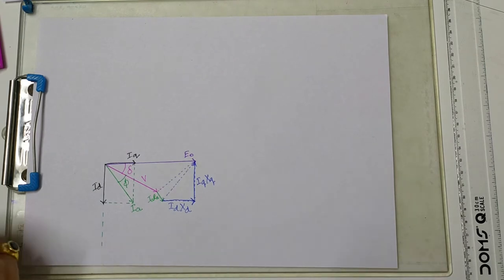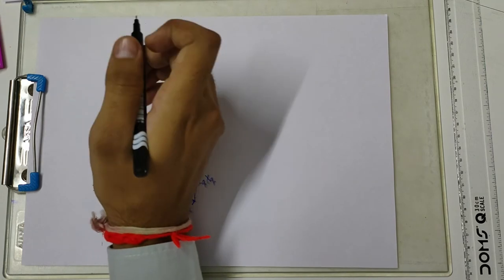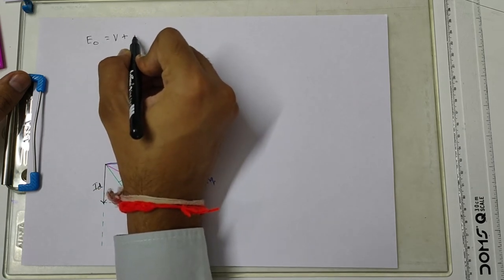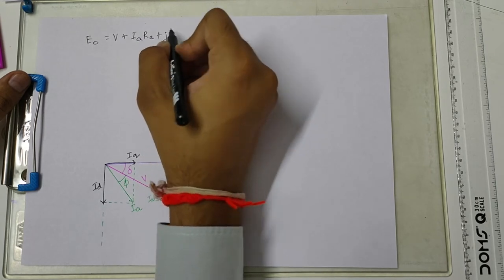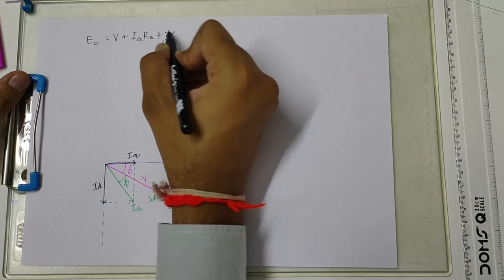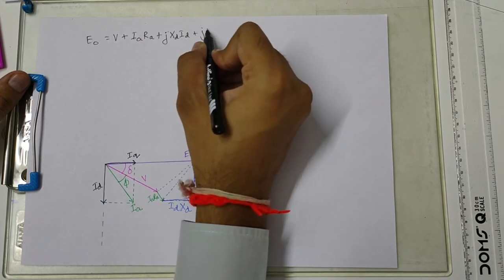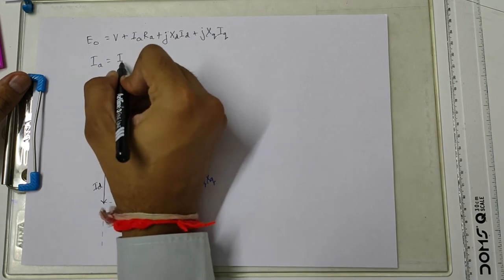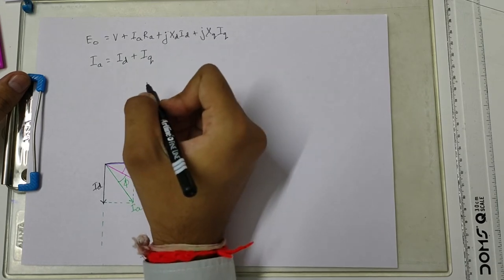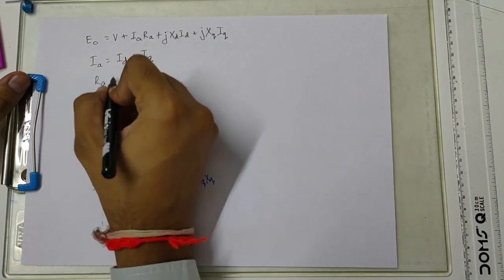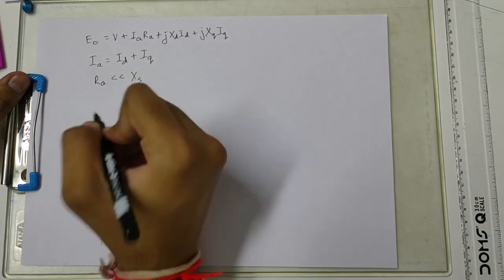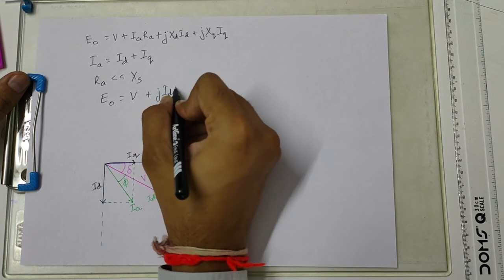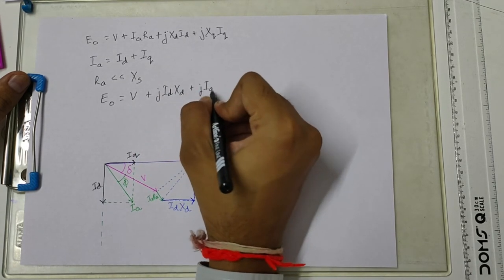We can write the equation from the phasor diagram as: E0 = V + IA·RA + j·XD·ID + j·XQ·IQ. We can also write that IA = ID + IQ. If we neglect RA, assuming RA is very much less than XS, then: E0 = V + j·ID·XD + j·IQ·XQ.